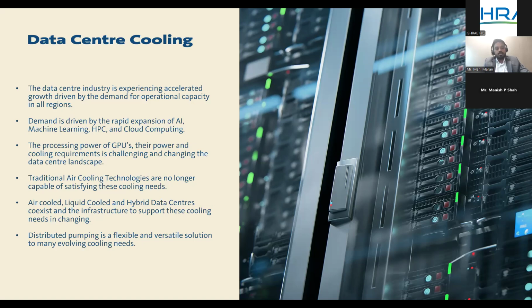So the cooling capacity we are seeing today, because of the modern advancement in GPUs, is tremendous. If we go back a year and look at the GPUs that were available at that time, and at the density of the server rack, we used to talk about 13 to 17 kilowatt per server. To remove heat of such capacity, traditional air cooling technology was doing a wonderful job. But seeing the growth in the capacity of GPUs and the amount of heat we need to remove from the system and from the server today, air cooling technology is no longer efficient.